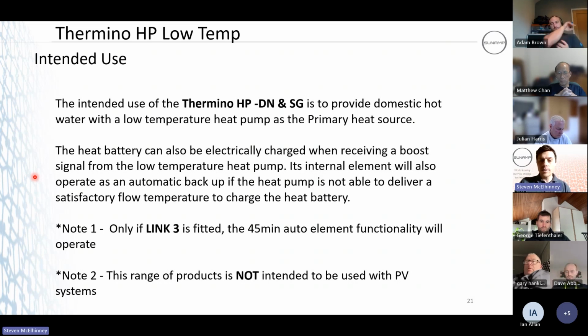What will happen is, after 45 minutes, the heat battery will recognise it's not up to temperature, and then it will bring on its internal element to boost it. So if you've got a 55-degree flow temp and it's running, you're essentially preheating that battery up to 55 degrees. The element will kick in and bring it up to temperature the rest of the way. One thing to note is these products aren't intended to be used with PV systems as well. So just remember that.